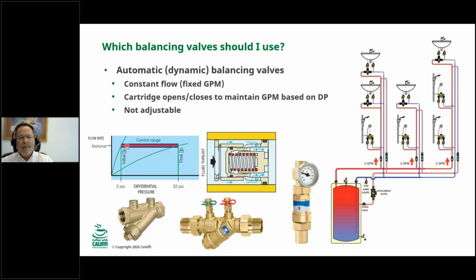They're not adjustable. If you order one and install it and you decide later, well, that's not the right GPM, you have to take it out and replace that cartridge. Some of these have a kind of a Y body, and you can just pull the cartridge out and put a new one in if you didn't install the right one in the first place. So they're inexpensive. They work great. For a designer, it's nice if he or she knows for sure that they want a given GPM in a given circuit. They're a great solution. And you can use these with a constant speed pump as well.